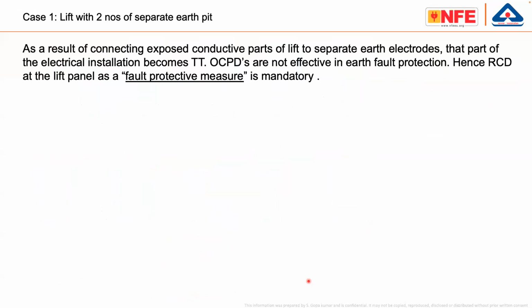Now, just to explain again, a lift with 2 numbers of earth pits. As a result of connecting exposed conductive parts of the lift to a separate earth electrode, that part of the electrical installation becomes TT. That part, not the whole electrical installation, becomes TT. OCPDs are not effective in earth fault protection. Hence, an RCD at the lift panel as a fault protective measure is mandatory, not additional protection.